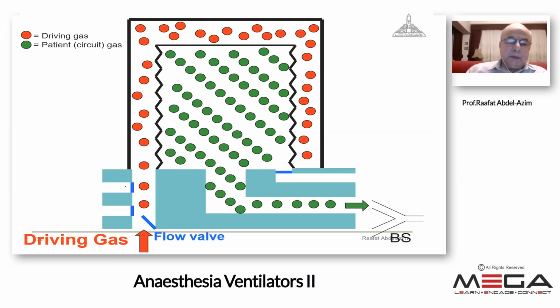It will be open for safety, and I adjust the pressure according to the patient's condition. Usually we start with 40 or 35 centimeter water. The gas coming through this overpressure valve is pure oxygen, and it will go into the atmosphere. The other valve is the exhaust valve that opened during expiration.